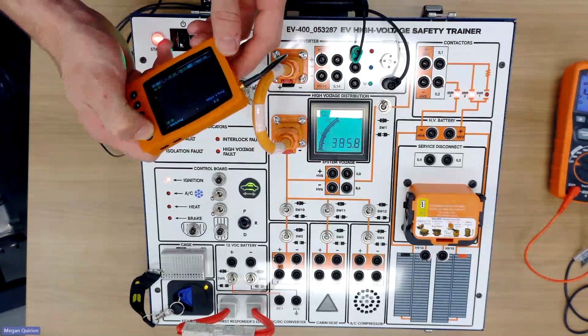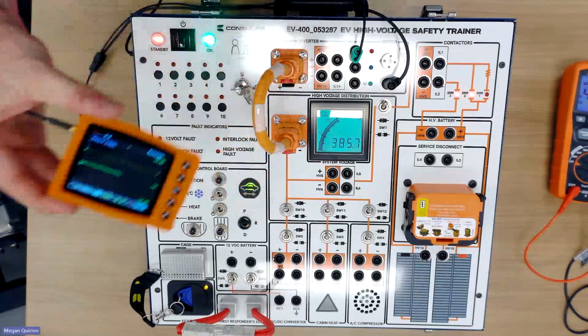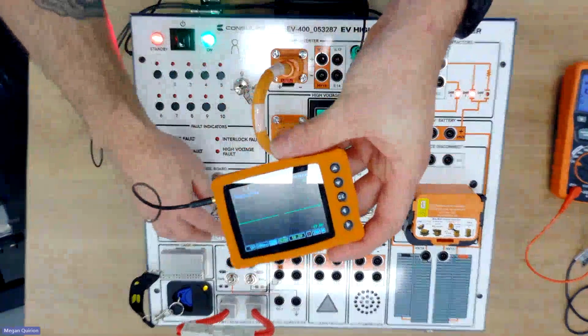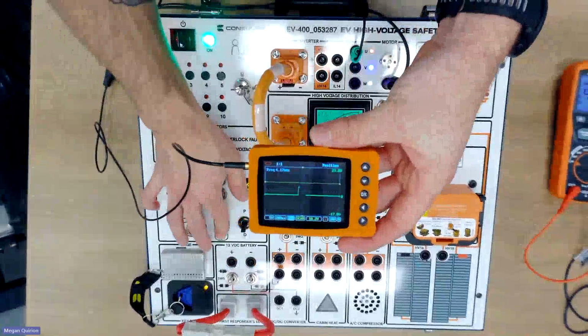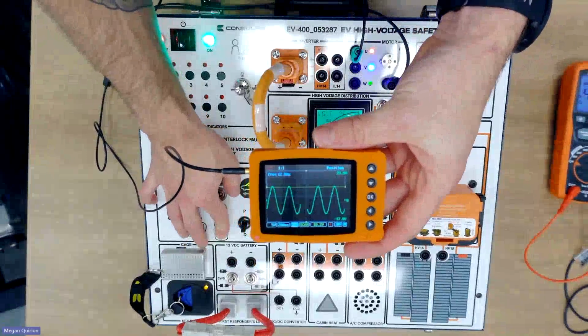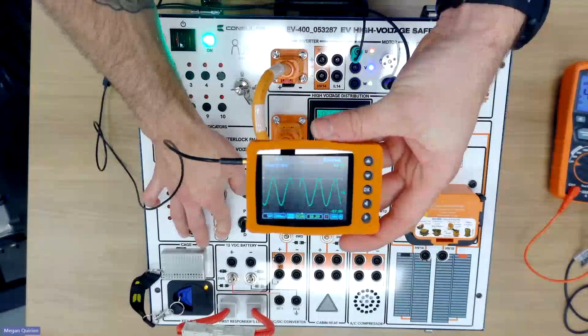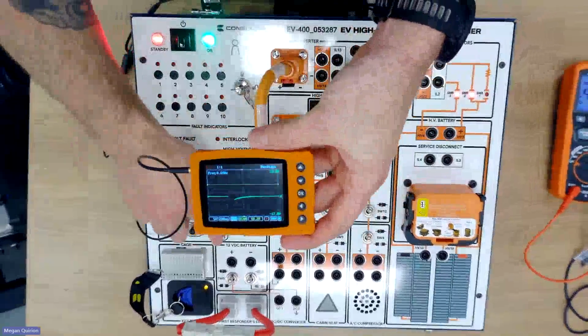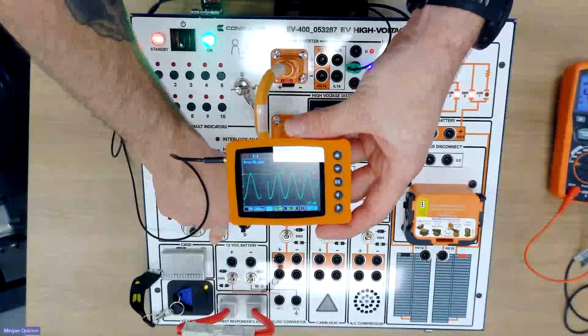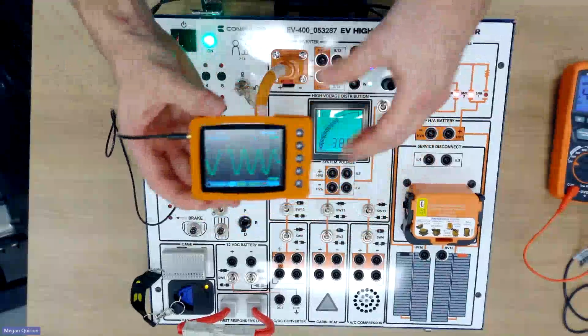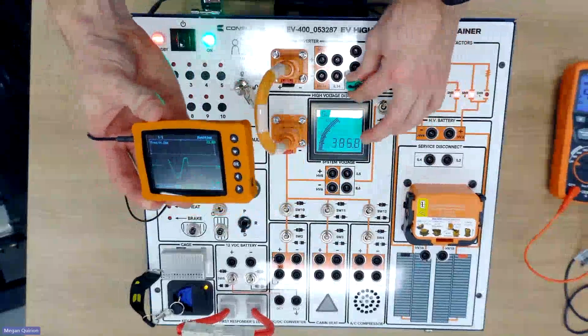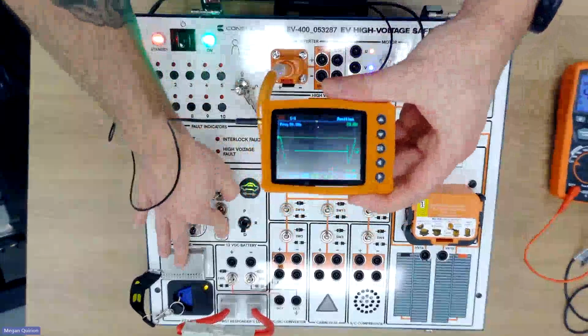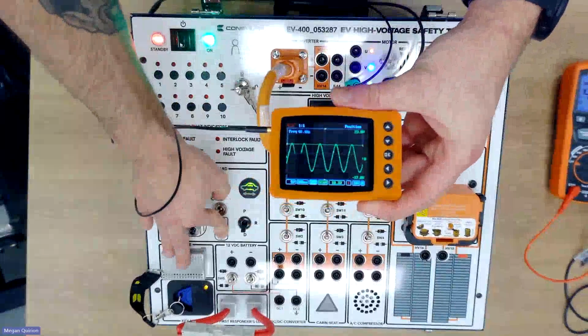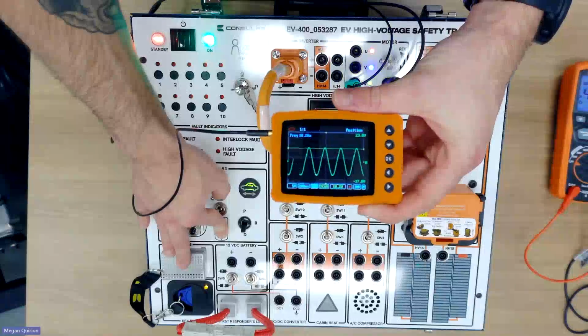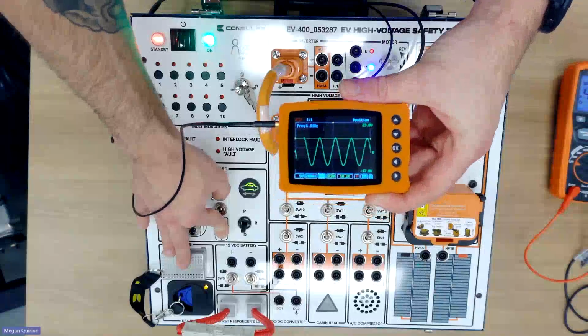This is only a single-channel lab scope, so we're only going to see one of the channels at a time. As he powers it up, you'll see the sine wave generated by the inverter to the stator, and he'll move through each one. If we had a multi-channel lab scope, each of these phases would be offset by about 120 degrees. In this case, we can check to see all three phases are working and that the amplitude is correct, but without a multi-channel lab scope, we can't superimpose them.